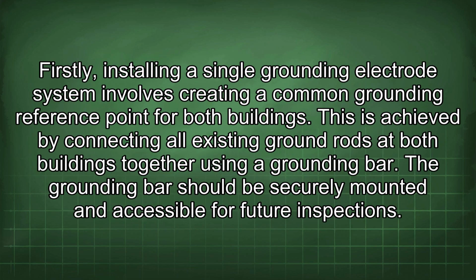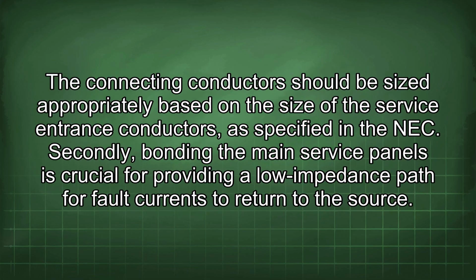Firstly, installing a single grounding electrode system involves creating a common grounding reference point for both buildings. This is achieved by connecting all existing ground rods at both buildings together using a grounding bar. The grounding bar should be securely mounted and accessible for future inspections. The connecting conductors should be sized appropriately based on the size of the service entrance conductors, as specified in the NEC.